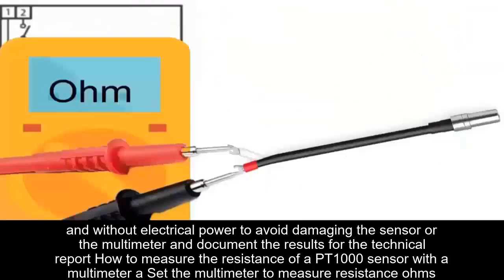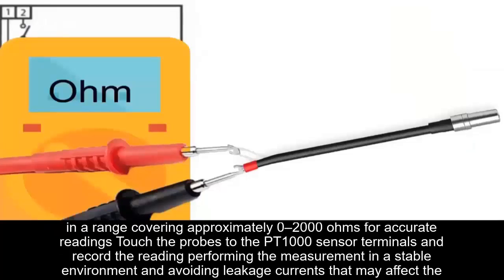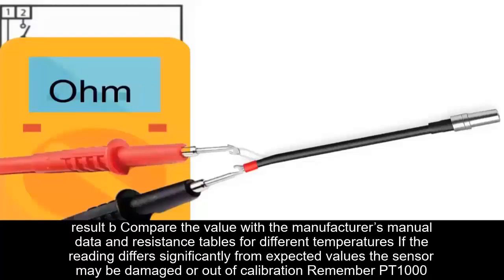How to measure the resistance of a PT1000 sensor with a multimeter. A. Set the multimeter to measure resistance, ohms, in a range covering approximately 0 to 2000 ohms for accurate readings. Touch the probes to the PT1000 sensor terminals and record the reading, performing the measurement in a stable environment and avoiding leakage currents that may affect the result.